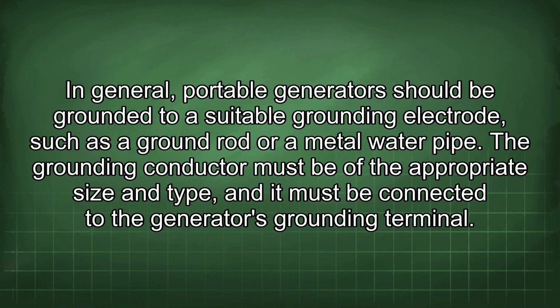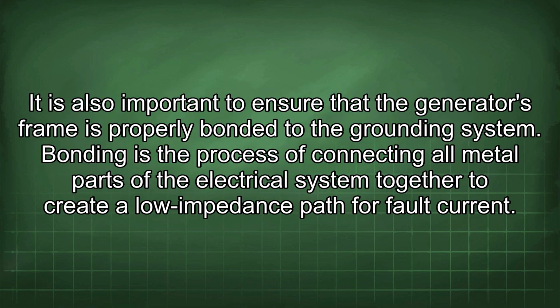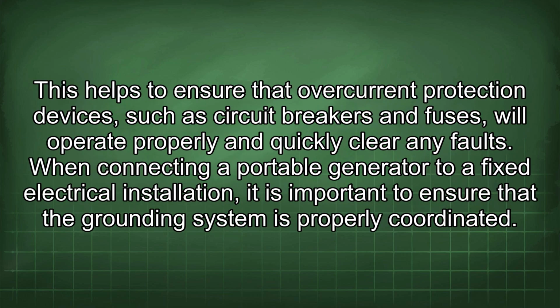In general, portable generators should be grounded to a suitable grounding electrode, such as a ground rod or a metal water pipe. The grounding conductor must be of the appropriate size and type, and it must be connected to the generator's grounding terminal. It is also important to ensure that the generator's frame is properly bonded to the grounding system. Bonding is the process of connecting all metal parts of the electrical system together to create a low impedance path for fault current. This helps to ensure that overcurrent protection devices, such as circuit breakers and fuses, will operate properly and quickly clear any faults.